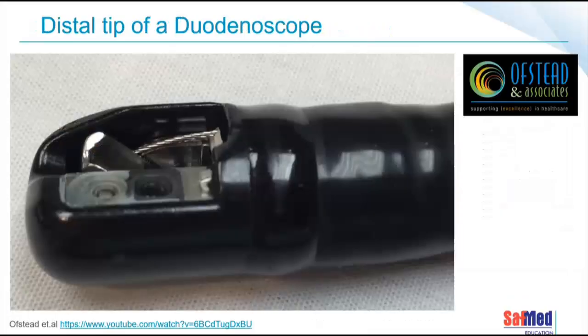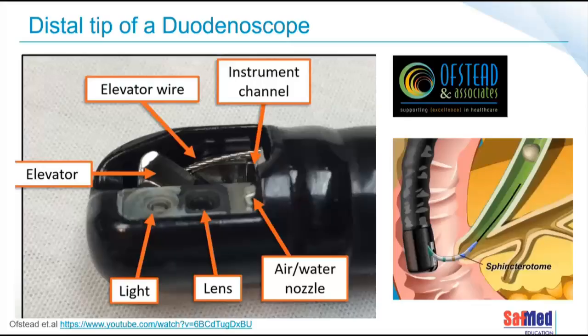Another very complex scope is that of a duodenoscope. And we're having a look now at an image, the distal tip of a duodenoscope. And remember I said it's a side viewing scope. Looking at the arrow, you can see where the lens is, where the light is, where the elevator wire is, where the air water nozzle is. Now that elevator is very, very important. We need to be able to insert items into the biliary tree. And to do that, we need to get round a corner. And to get round the corner, we need the elevator to pop up.